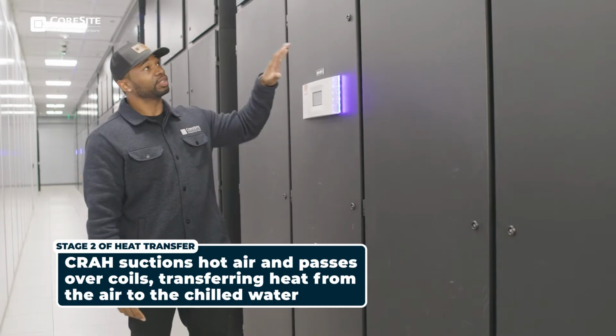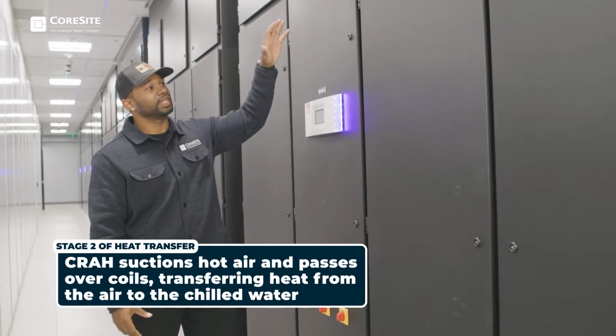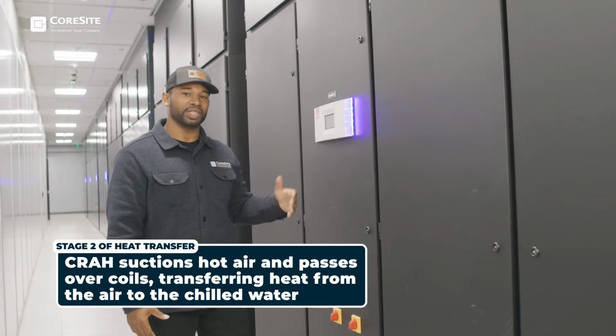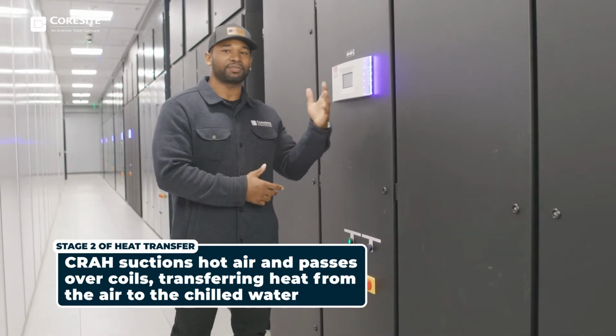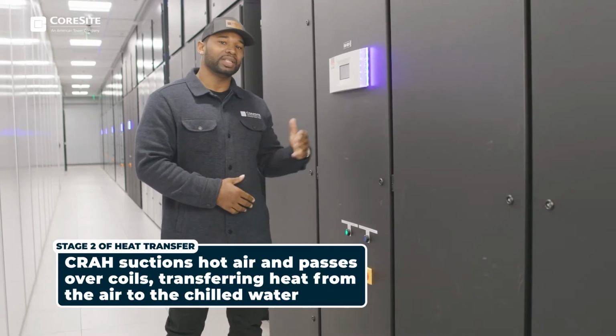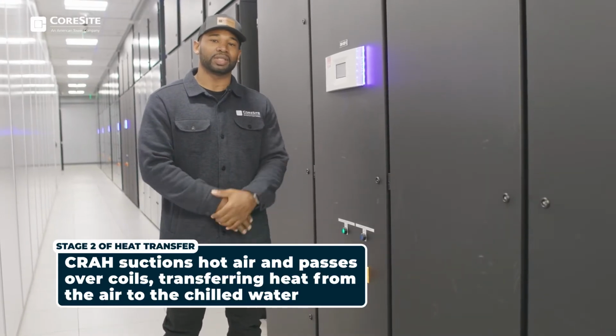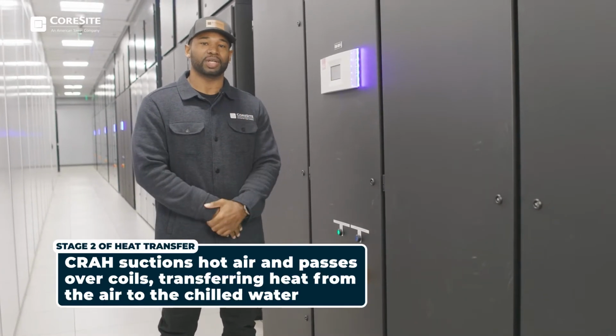The second stage of heat transfer happens right here at the CRAH. The CRAH takes suction from the hot air plenum. That hot air passes over the coils containing chilled water, transferring heat from the air to the chilled water. That chilled water is then pumped back to our chillers, where the third stage of heat transfer takes place.